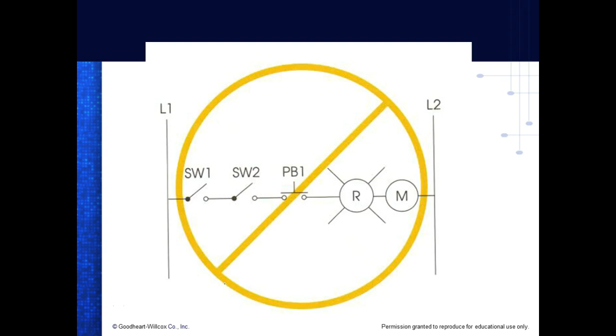Yes. If you've got a magnetic motor, if you've got a motor that doesn't have overloads. Now a lot of your motors, we call them in industry, we have multiple voltages available out there. And of course, the higher the voltage, the less current's required to produce that horsepower, right? You understand? So we have what we call multi-voltage motors. Usually they're dual voltage motors. And what we do is we literally rewire it to run on a high voltage, or we rewire it to run on a low voltage. So what that does, it allows the plant to have one spare motor that actually can run on two different voltages. Well, what happens is that your overload size is dependent on how much current you pull. So if you wire it for high voltage, the motor needs less current to produce the horsepower, right? You understand that. If you wire your motor for low voltage, it requires more current.